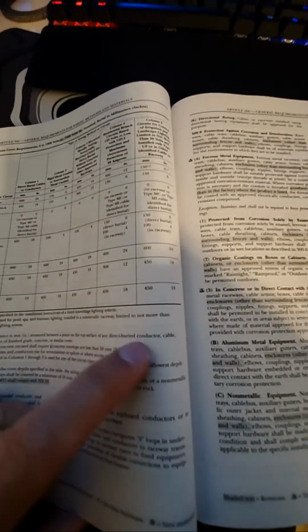300.5 is your burial depths. What we're going to see if we look through all of these notes, because these notes are very important, it tells you how to measure. So the cover shall be defined as the shortest distance measured between the top of the conductor or cable or conduit to the finished grade. So if you got to get a burial depth of 6 inches, for example, and you dig your ditch only 6 inches deep, your raceway is going to be at least 1 inch tall. So you lose, technically, if you upset the inspector. If you upset me, I'm going to call that all day. So if you want to cover up the ditch before I get to inspect it, and then I come back with my tape measure, and it's 17 inches to the top of the raceway instead of 18, you shouldn't have buried the conduit without the inspection. That's all I'm saying.